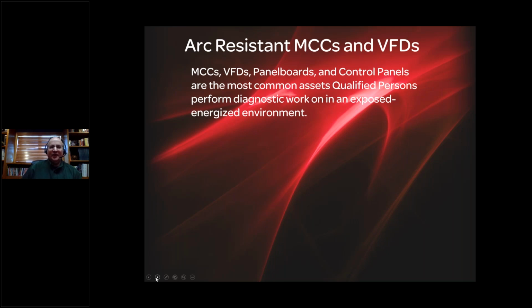And why is that? It is because these are the two assets, and you can add panel boards and control panels to that list, but MCCs and variable frequency drives are the majority of the concern in terms of arc flash risk. These are the two assets that qualified persons are most commonly working on in an exposed, energized manner for testing, troubleshooting, and calibration. Those three tasks fall under the diagnostic work definition of NFPA 70E.